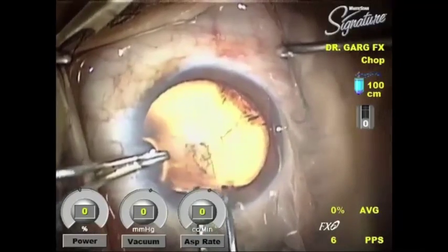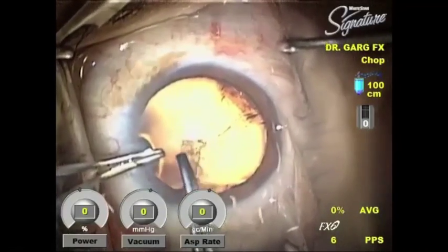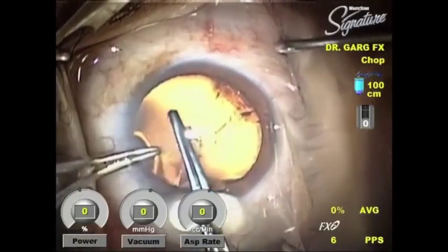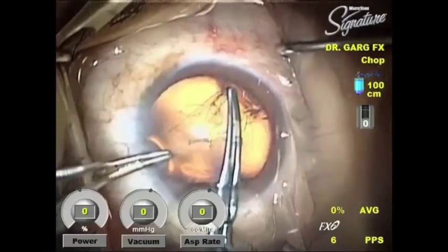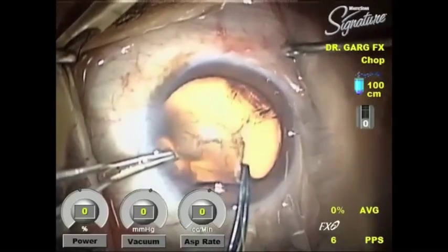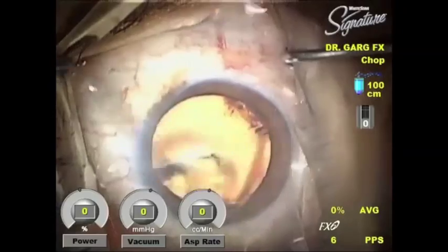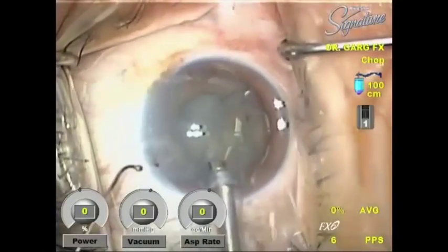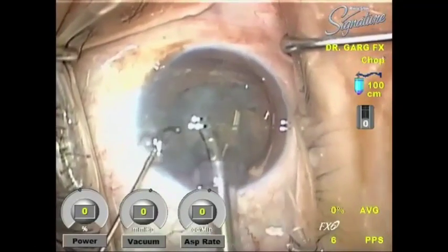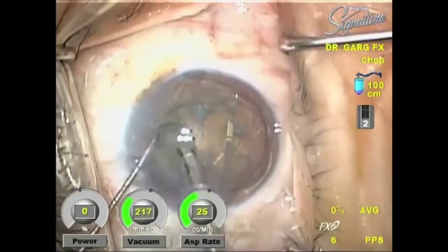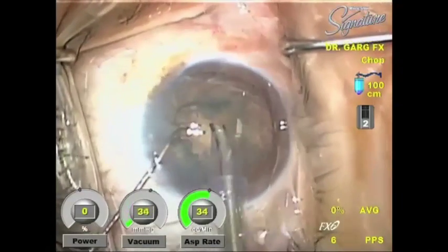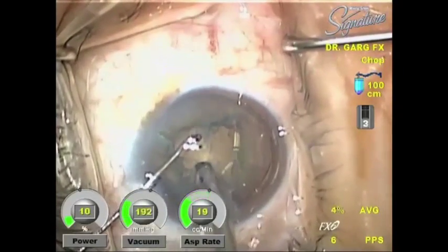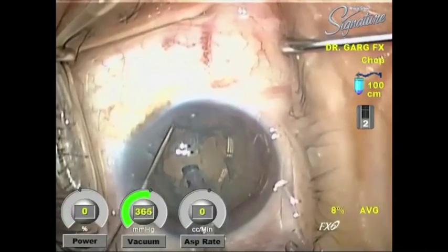With a peristaltic pump, you control the aspiration rate, and the vacuum is a function of how much occlusion you have at the tip, which is different than the Venturi pump, in which vacuum is always live at the tip. So in this case now, I'm going in with my Phaco probe, and I'm cleaning up a little bit of the cortical material on top of the nucleus, and then I impale and again do a horizontal quick chop.